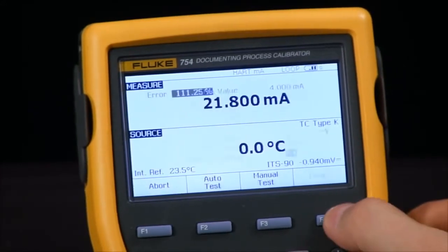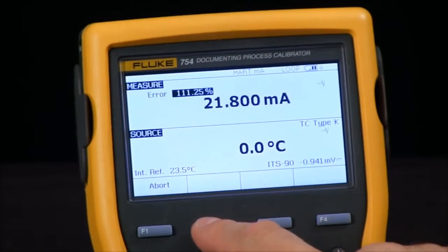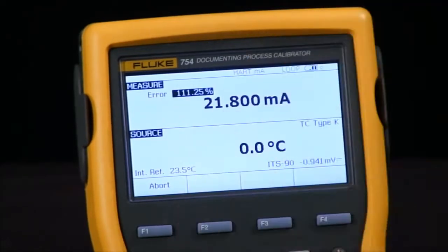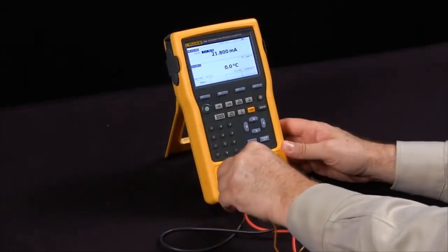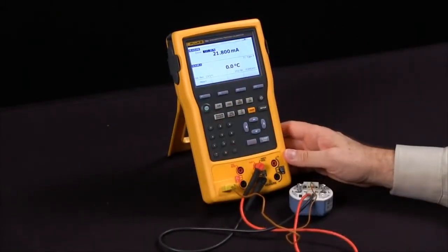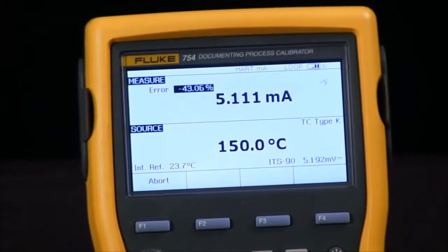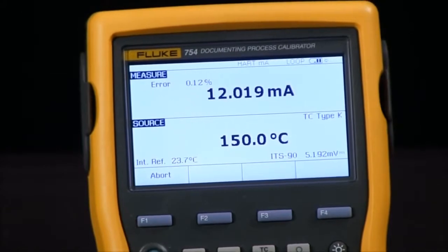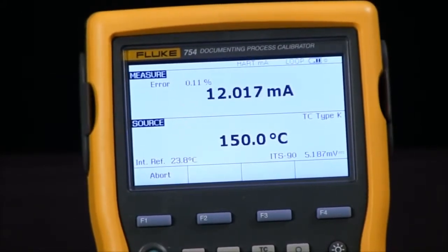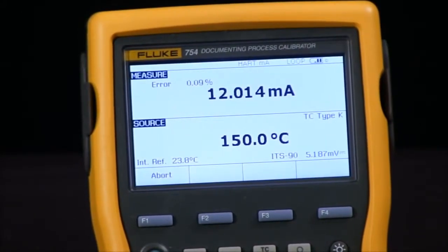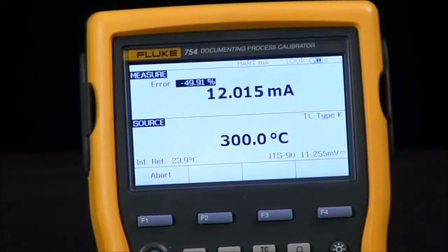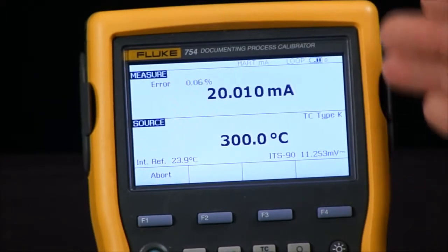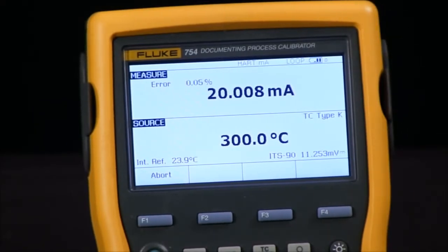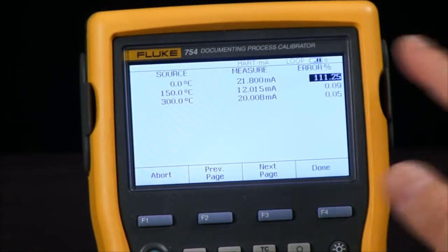What I can do now is just start an auto test. And the 754 will source through the thermocouple, and it will read back the milliamp values. This will take a few seconds because I do have the 10-second delay built into it. And as soon as it is done its progression, it will give me the values for the test. And I should expect at least one of them to be out of tolerance because I did not connect a thermocouple on purpose. So there I am.